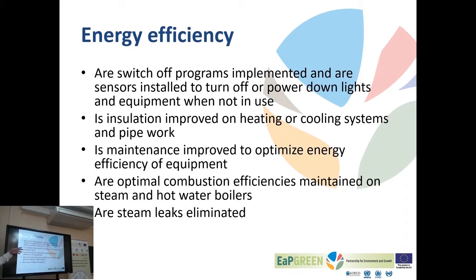Improved insulation of cold storage. Sometimes buildings have been expanded, floors are not insulated, the roof is not insulated well. Many plants, there is a lot of potential in better insulation of the facilities, but also of pipes. Pipes carrying chilled water as well as pipes carrying hot water. Steam pipes sometimes are not lagged properly. Valves, flanges are not lagged at all.